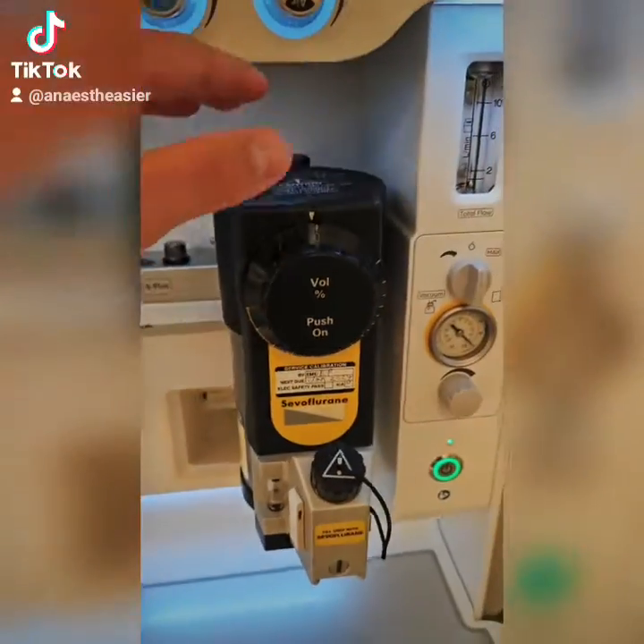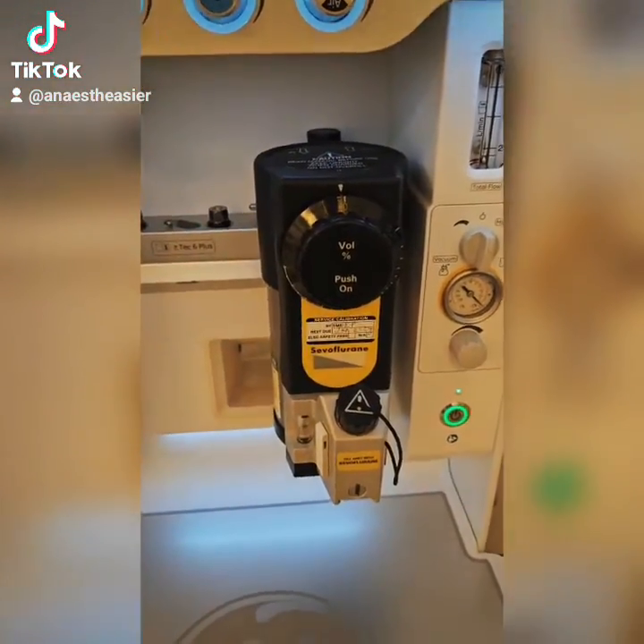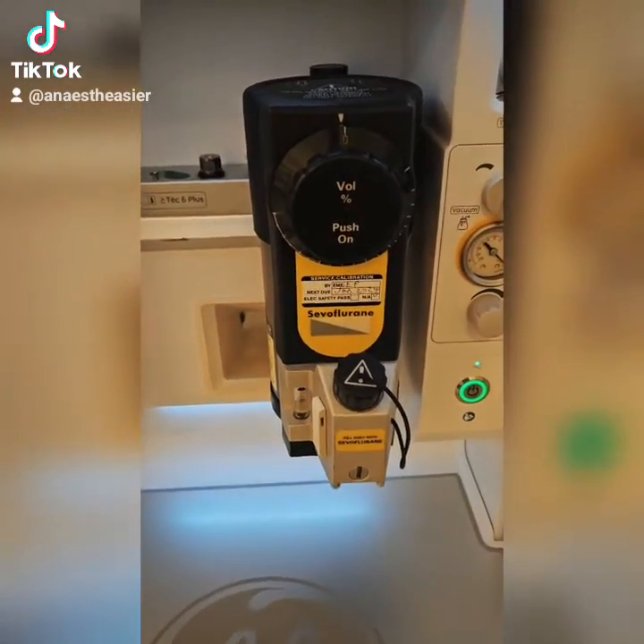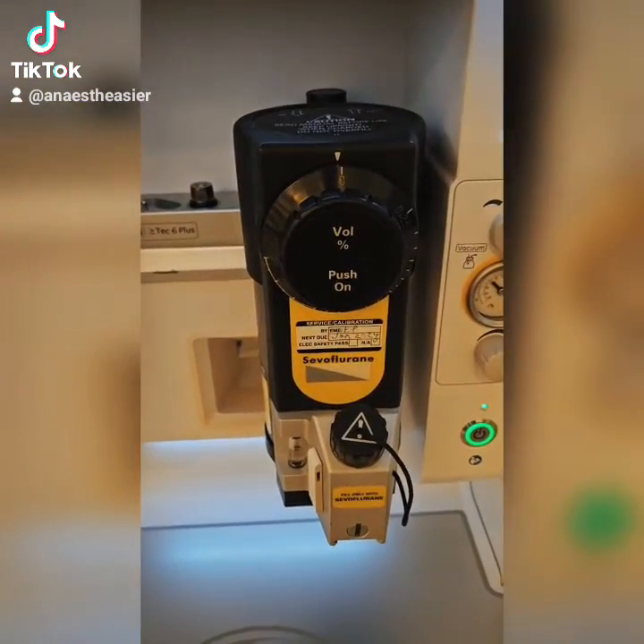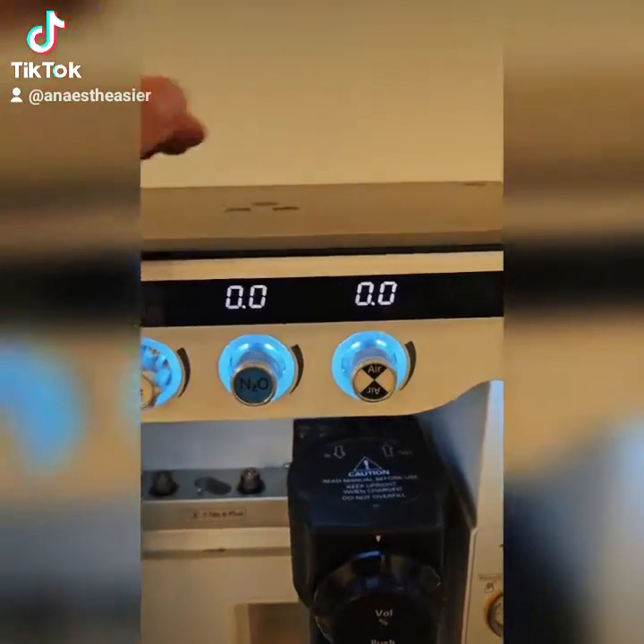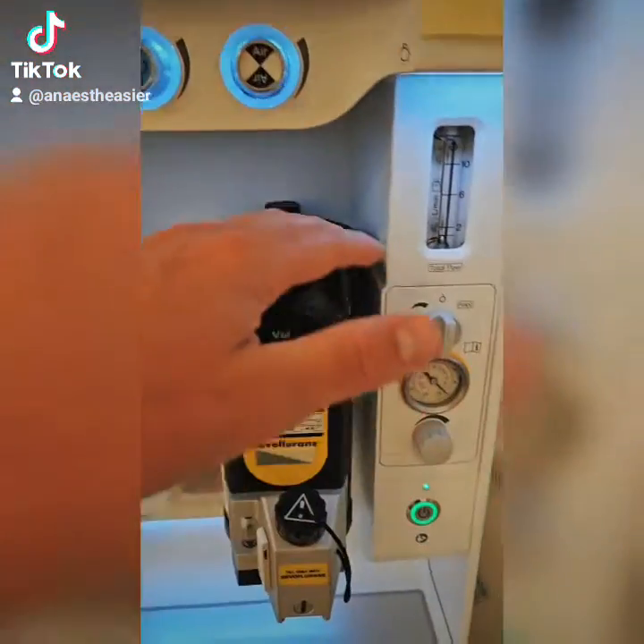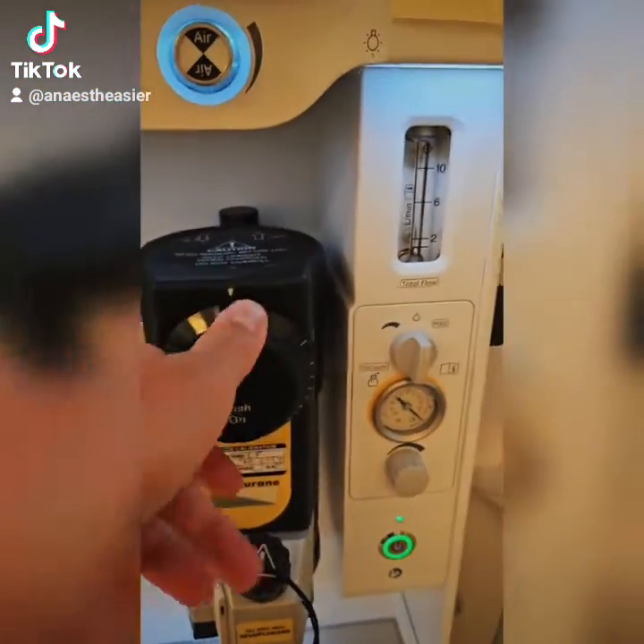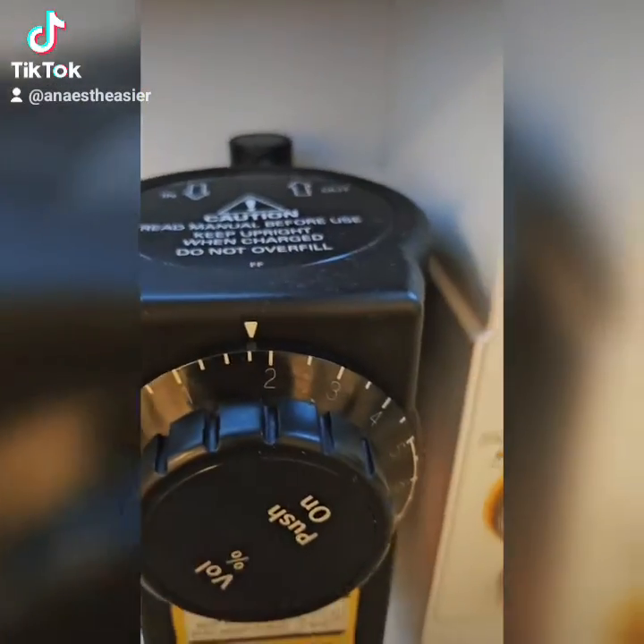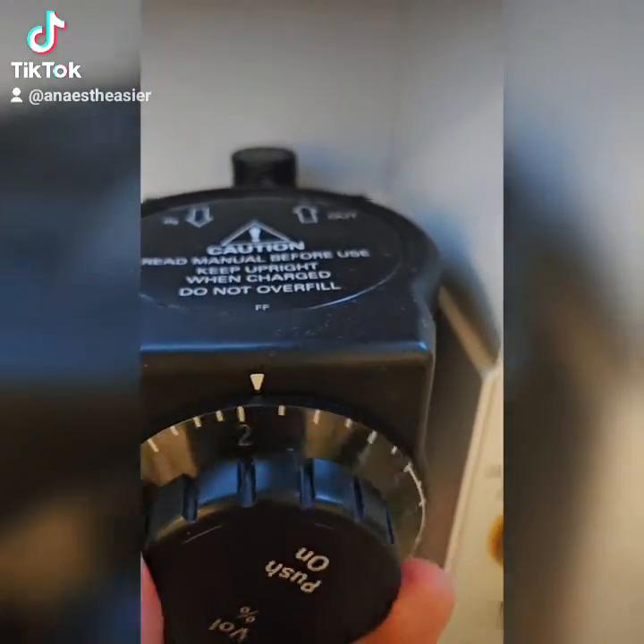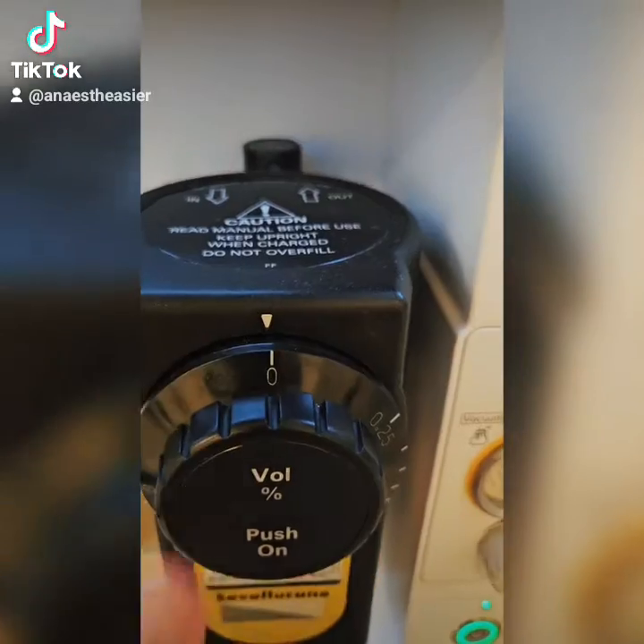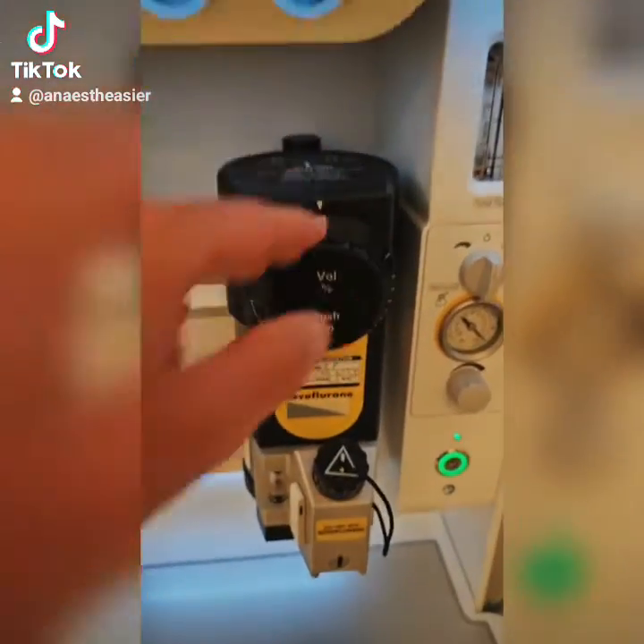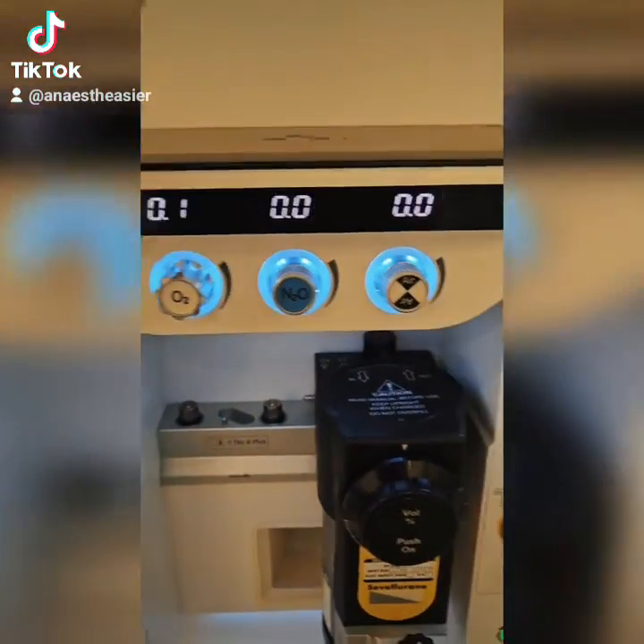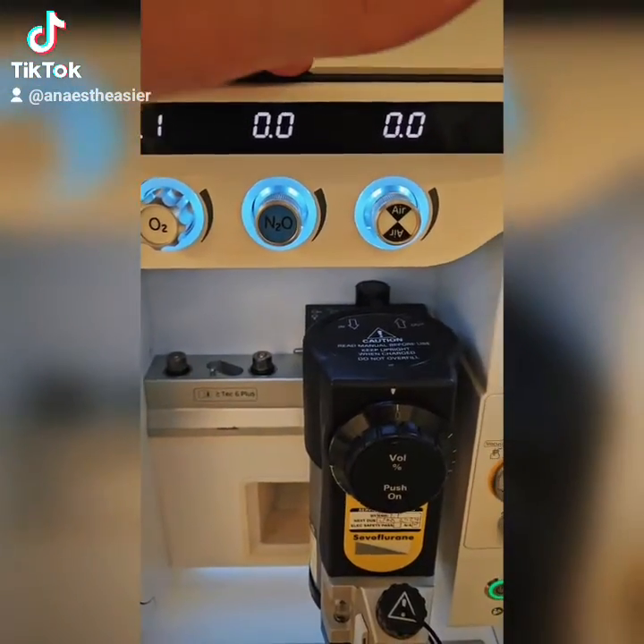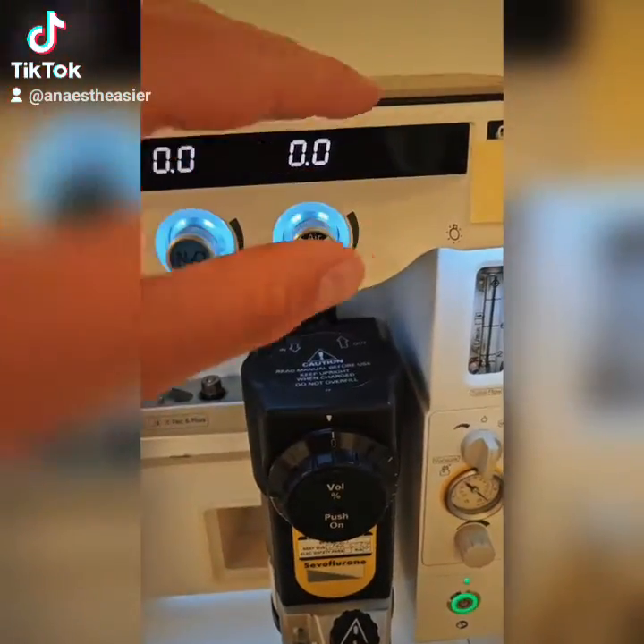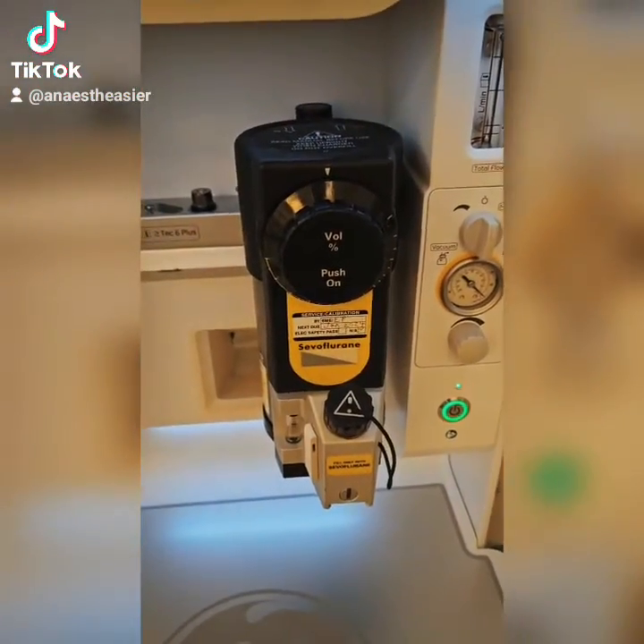And then what this does is calibrates how much sevoflurane is being given into the breathing circuit. So you've got your mixture of gases that you want to give, and then you add in how much sevoflurane you want to give. And all you do is push this dial, and that has gradations on it which tell you what concentration of sevoflurane you're giving to the patient. This is what keeps the patient asleep. Obviously oxygen keeps them alive, nitrous will add to pain relief and reduce how much sevoflurane you need, and air you just use to make up what flow rate you want.